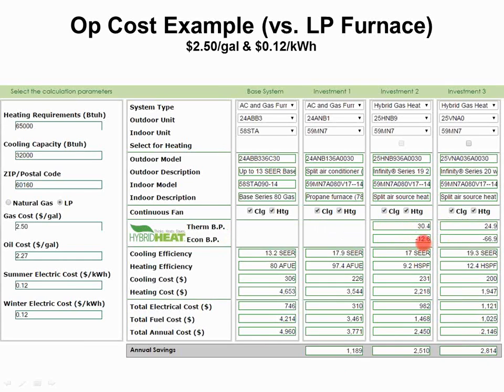Now it's a negative 12-degree break point for the first heat pump, negative 66 for the second one. It basically says economically, you should never turn this heat pump off. Just keep running it forever and ever. Now, because my thermal break point is at 25 degrees, I have to switch my heat pump over at that point just to get the BTUs that I need, or something close to that. Maybe I'll switch it at 23 or something.